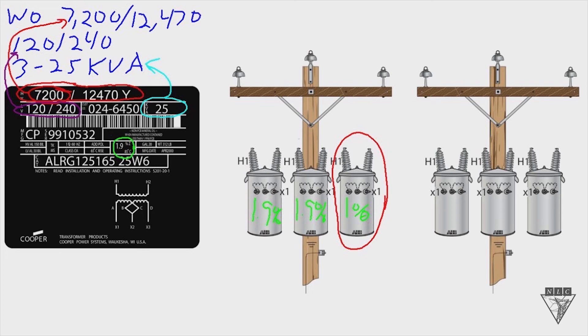So you want to try and find three transformers that have impedance that are very close together. Some companies will give it a plus or minus 5% range, but check with your company just to find out what they require.